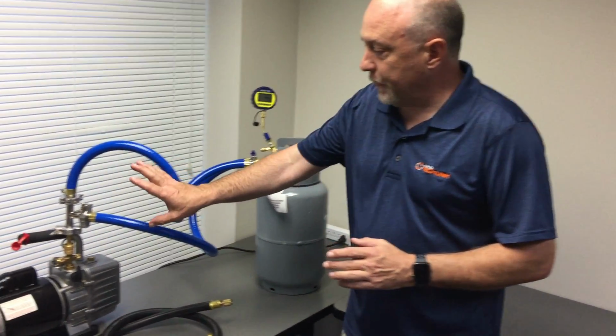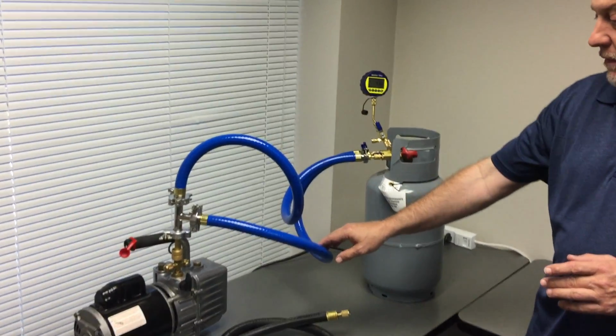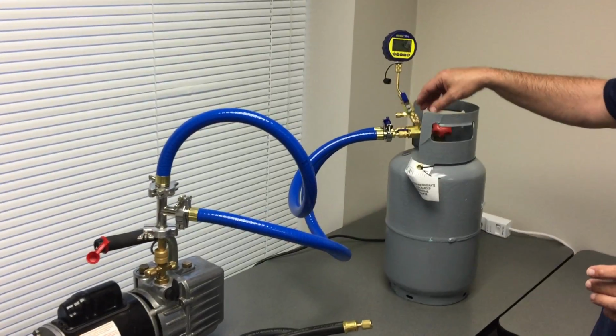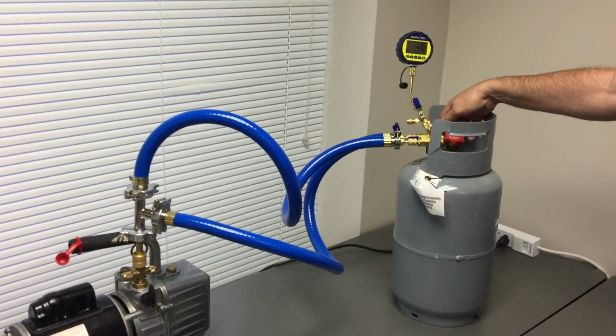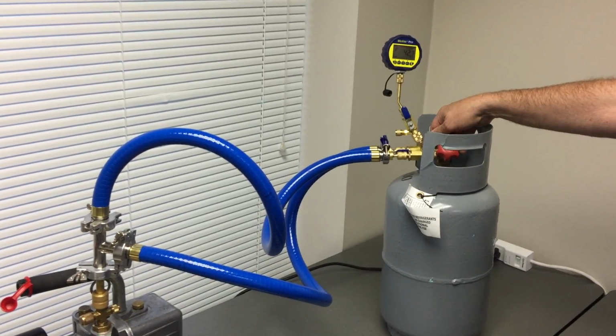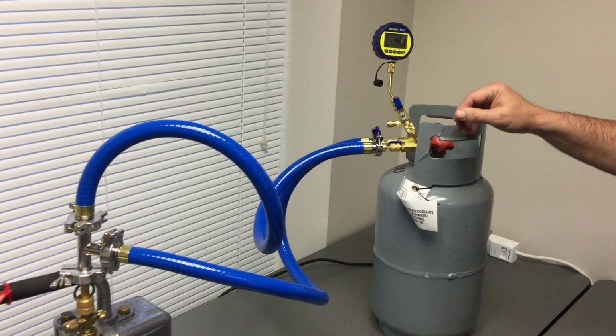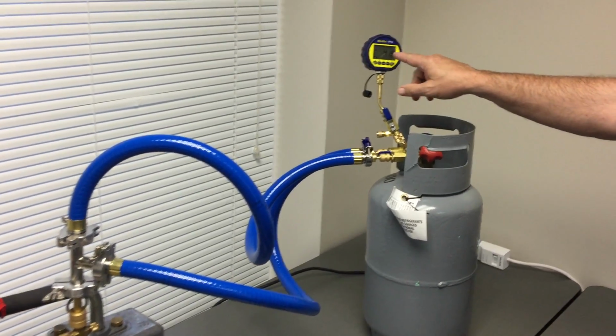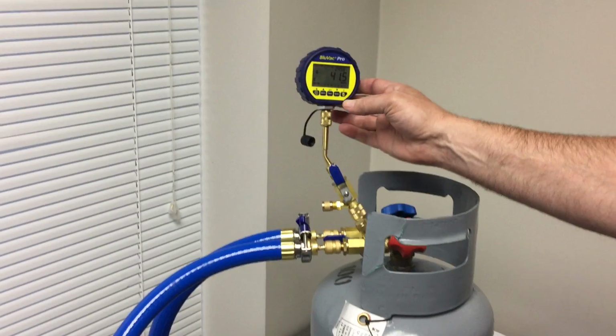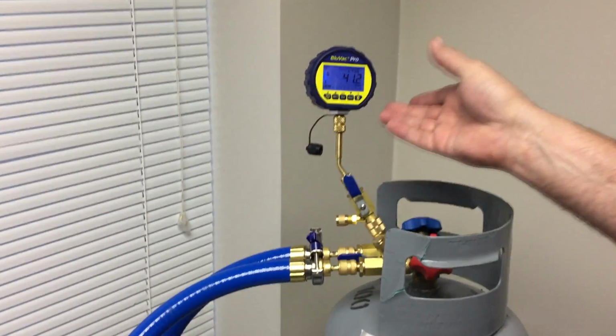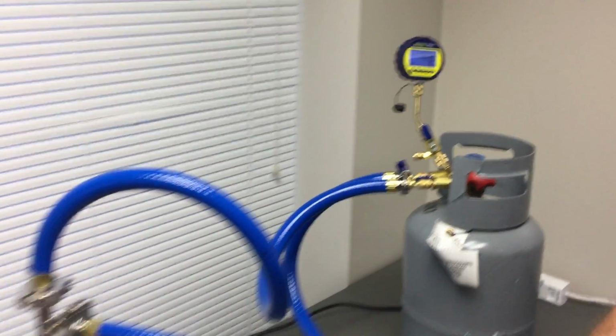So what I got hooked up here is just a regular JB vacuum pump, 7 CFM. I got it hooked up to a recovery tank. I actually had these closed off just so we can see the pull down on the hose because I want you to see some interesting characteristics right here. The vacuum gauge is down to about 41 microns here and still dropping. I just started this just a second ago. But let's take a look here on the screen.